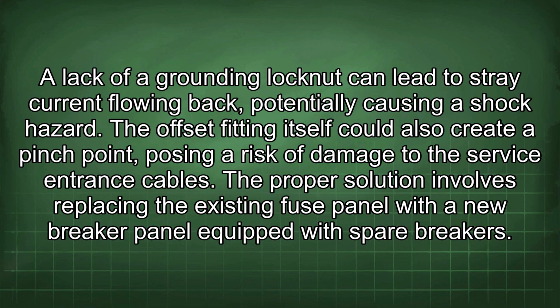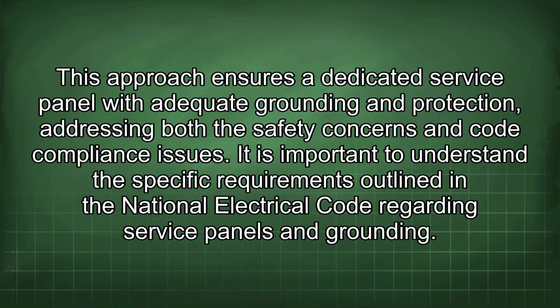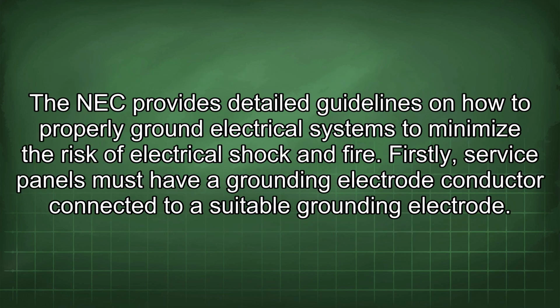The proper solution involves replacing the existing fuse panel with a new breaker panel equipped with spare breakers. This approach ensures a dedicated service panel with adequate grounding and protection, addressing both the safety concerns and code compliance issues. It is important to understand the specific requirements outlined in the National Electrical Code regarding service panels and grounding. The NEC provides detailed guidelines on how to properly ground electrical systems to minimize the risk of electrical shock and fire. Firstly, service panels must have a grounding electrode conductor connected to a suitable grounding electrode.